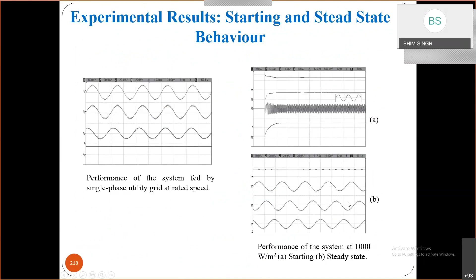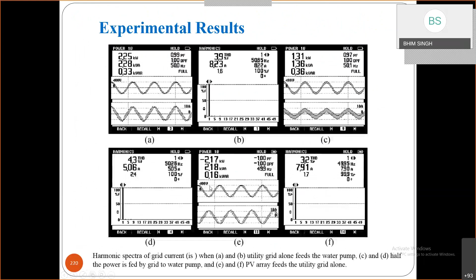And when the solar generation is less, power comes from the grid, and the THD on the grid side is less than 5% with unity power factor, while feeding power. Then we worked with the synchronous reluctance motor also, which is new. In the last 5 years only, ABB and Siemens started manufacturing it. We also manufacture it after designing with the help of industry.